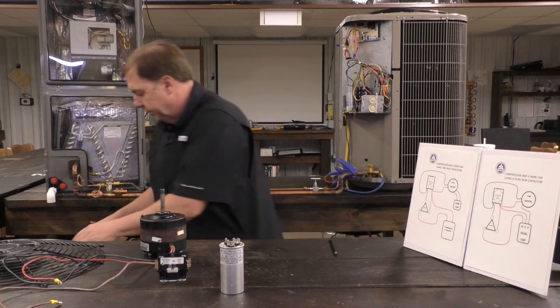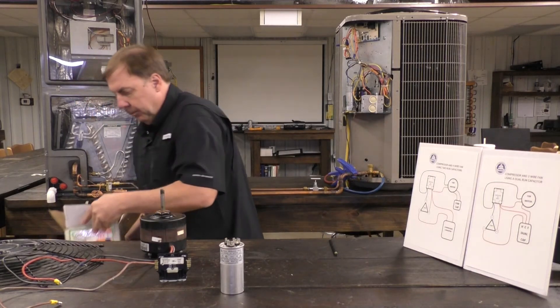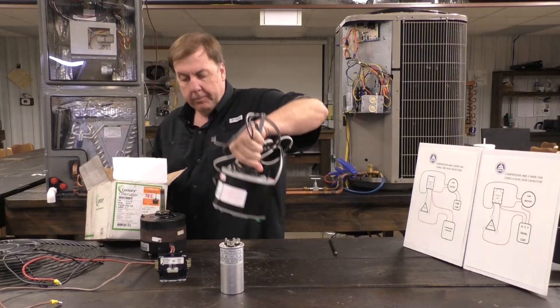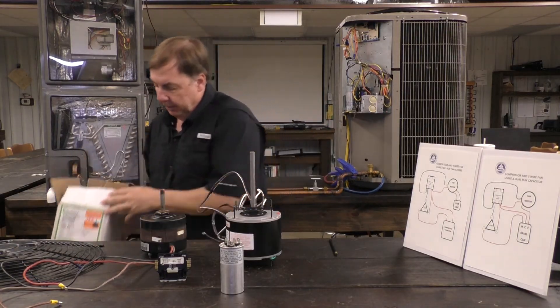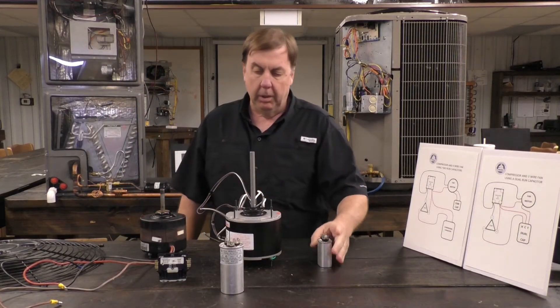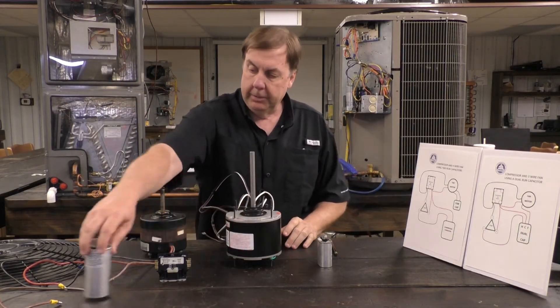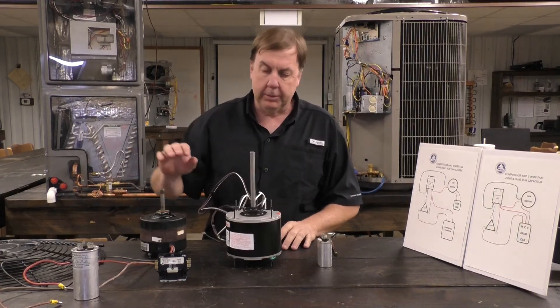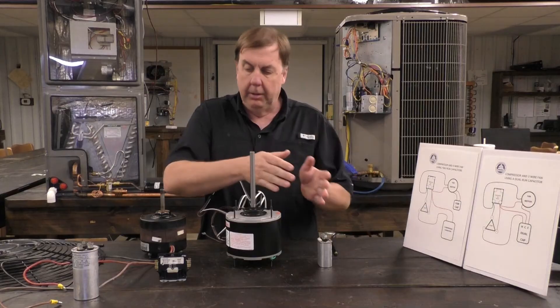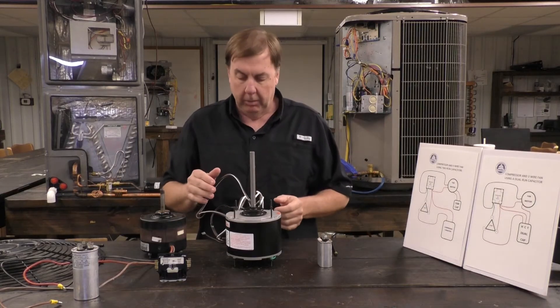I get my box with my new motor in it, get the motor out. With all new motors, we're always going to buy a new cap, so we're going to buy the right fan cap for the new motor. This cap's going to stay in place with the compressor wires, we're not going to touch it again. Now we've got our new motor, our new cap, and our contactor we've got to wire up.